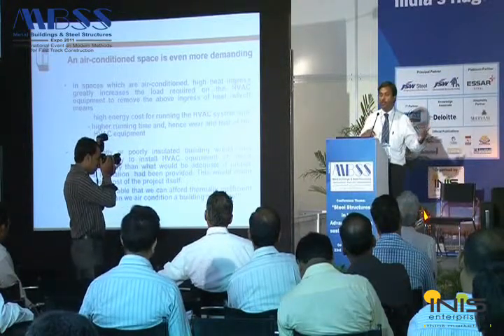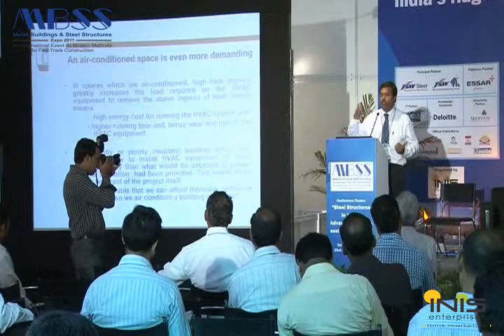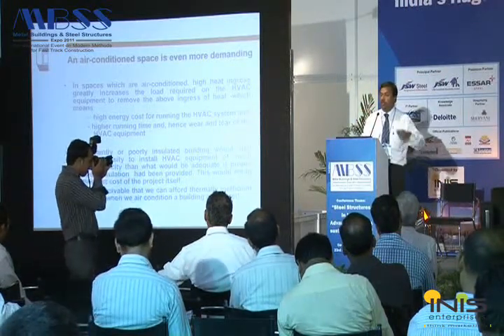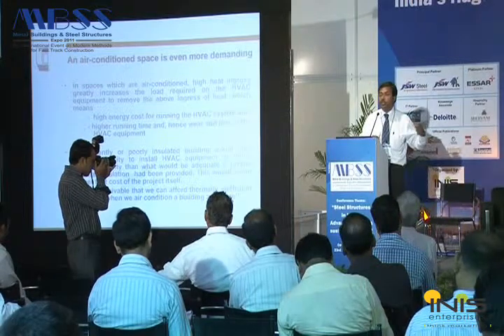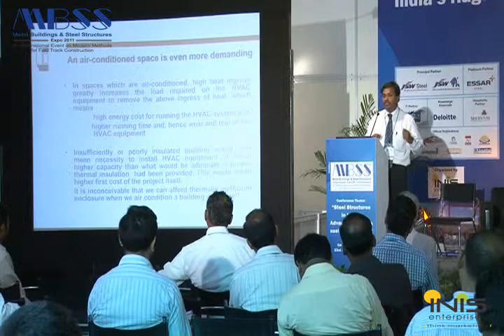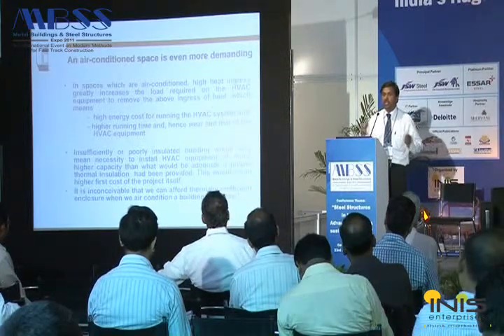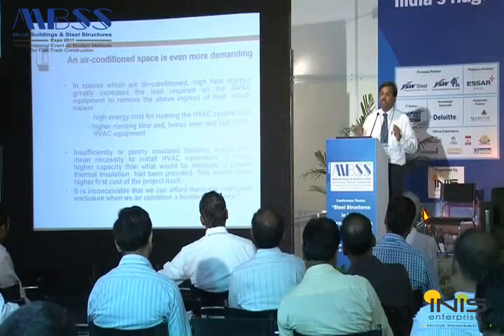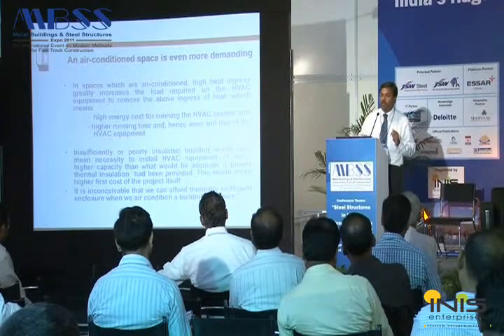Why? Because your compressor is trying to cool down the atmosphere inside, but heat is coming from the roof and the wall. So your running time of the compressor increases, and that is where you have a lot of increased energy consumption. We have seen by statistical figures that between an insulated and uninsulated building, the consumption of energy varies something from 30-35%, even to as high as 40%.